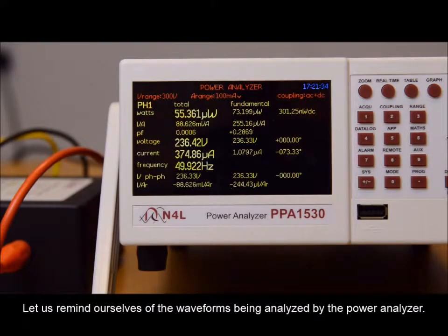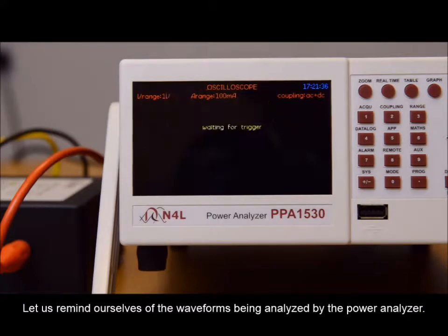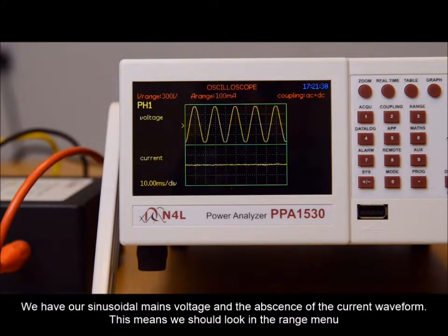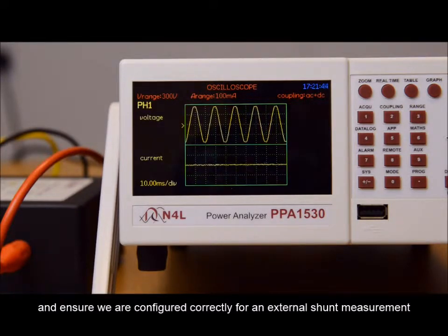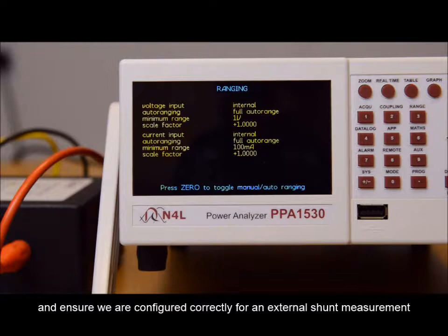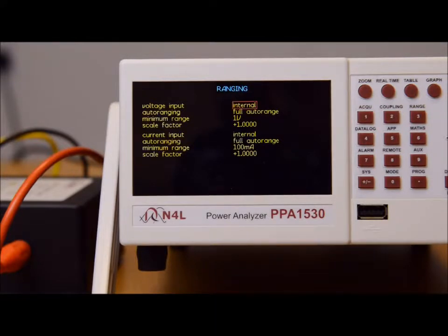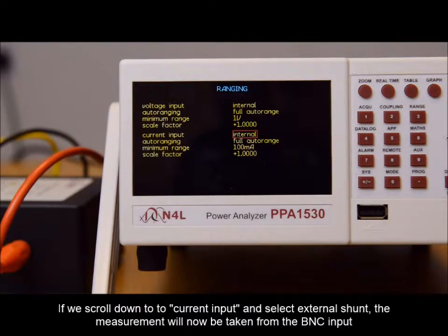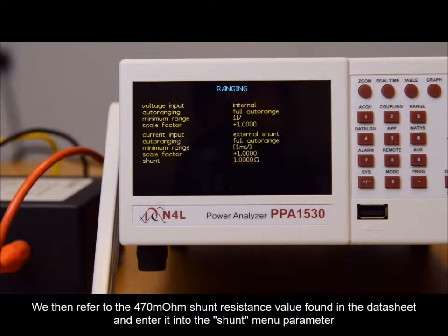Let us remind ourselves of the waveforms being analyzed by the power analyzer. We have our sinusoidal mains voltage and the absence of our current waveform. This means we should look into the range menu and ensure that we are configured correctly for the external current measurement. If we scroll down to the current input and select external shunt, the measurement will now be taken from the BNC input. We then refer to the 470 milliohm shunt resistance value found in the datasheet and enter it into the shunt parameter.